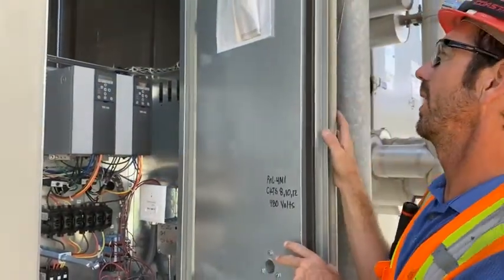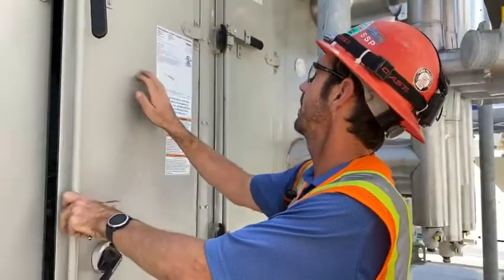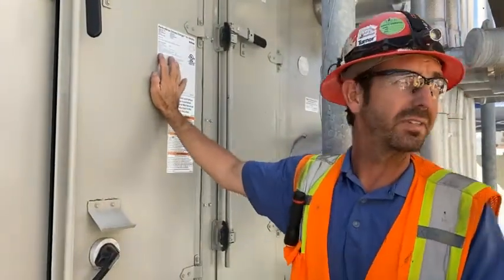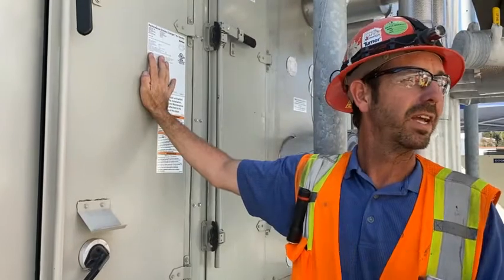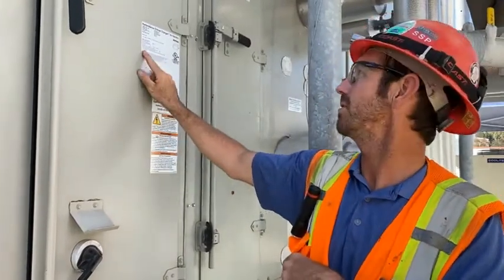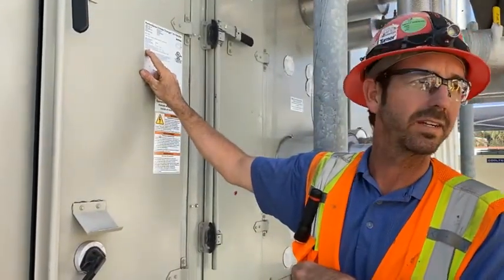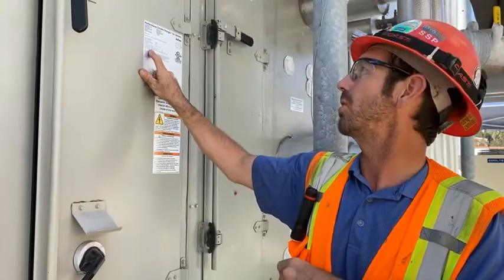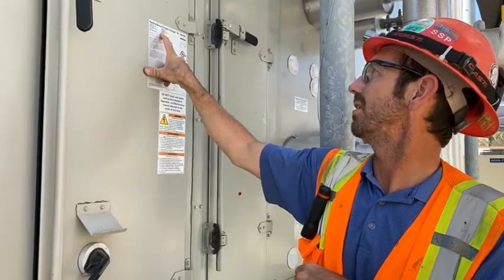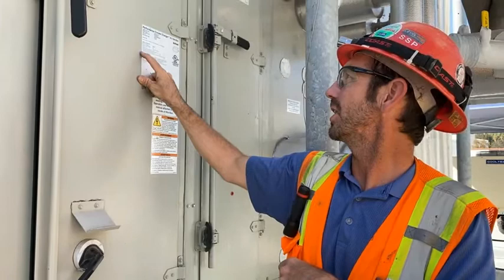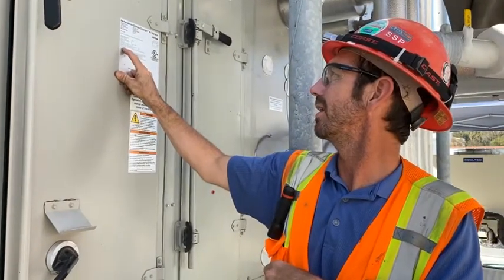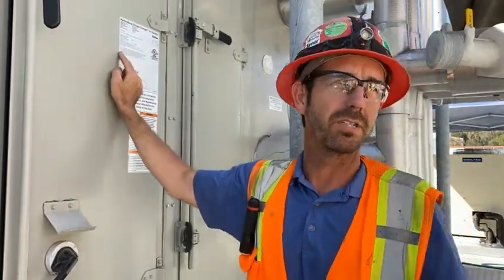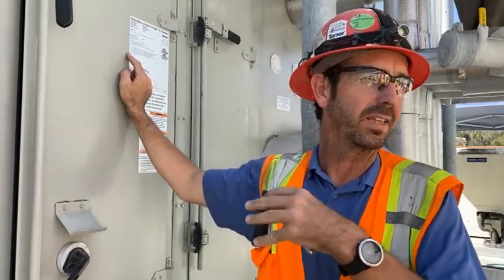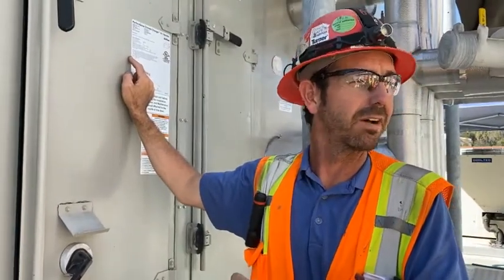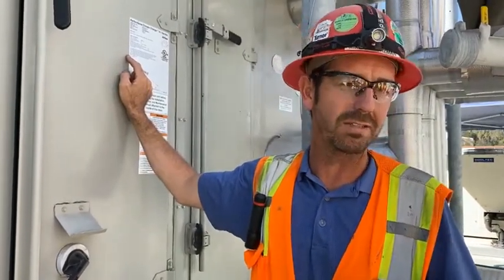Another super important thing on these Trane air handling units, these are special motors. These aren't off-the-shelf motors, okay? If a motor fails in this unit, you have to use this part number right here on the outside of the container. Or when you call Trane, make sure you get the model and serial number, but you need to make sure it's this part number right here, okay? These motors can be run over the horsepower rating that's stamped on the motor itself, okay?